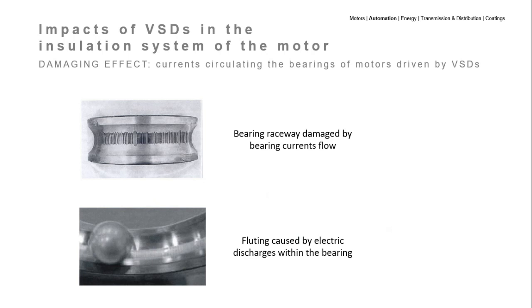These discontinuous electric discharges wear the raceways and erode the rolling elements of the bearings, causing small superimposing punctures. Long-term flowing discharge currents result in furrows or fluting, which reduce bearings life and may cause the machine to fail prematurely.